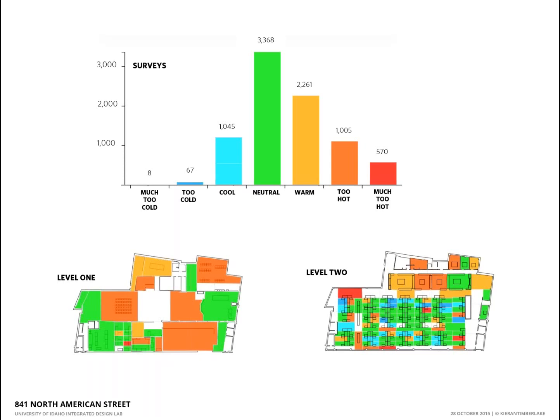The nice thing about having data is it was something that was absolutely definitive that says, the building is performing this way or that. And one of the things that we found is that a lot of the modes of operation that were dependent upon delivering underfloor air through a very large VFD indicated that the compression energy from that fan on that air was actually raising temperatures by about 5 or so degrees of that air that was getting pushed into the building. When you have a 5-degree increase in outside air temperature, if you're bringing it in, plus you have internal gains, it really starts to undermine the effectiveness of an all-passive strategy.